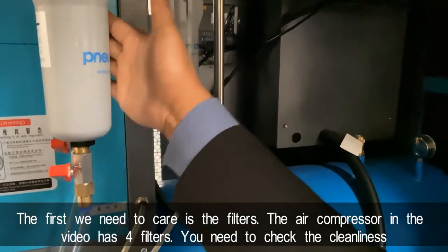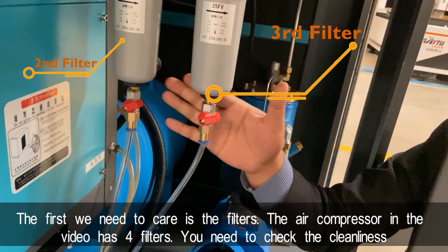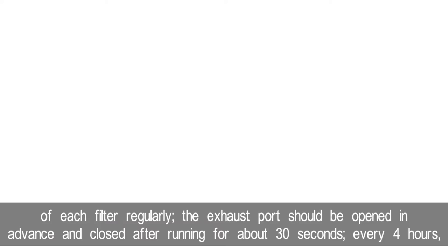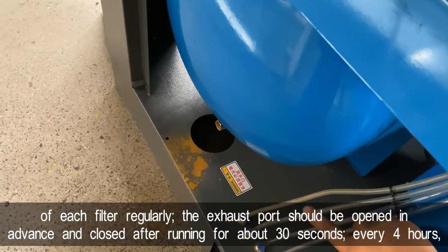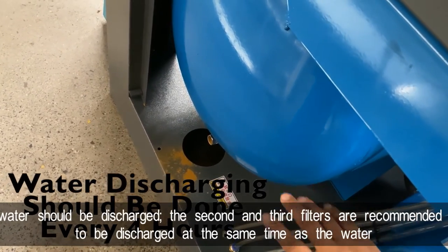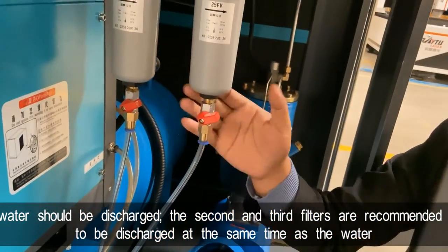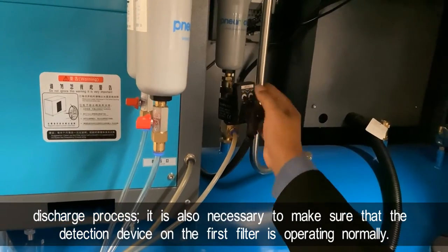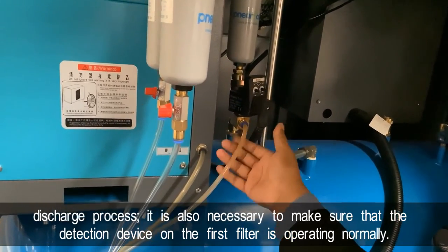The first thing we need to check is the filters. The air compressor in the video has four filters. You need to check the cleanliness of each filter regularly. The exhaust port should be opened in advance and closed after running for about 30 seconds. Every four hours, water should be discharged. The second and third filters are recommended to be discharged at the same time as the water discharge process. It's also necessary to make sure that the detection device on the first filter is operating normally.